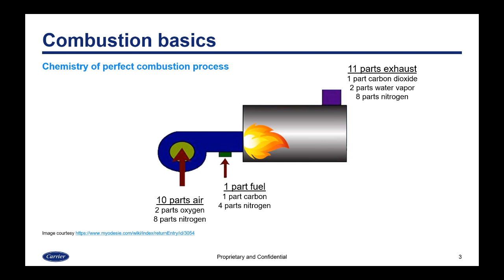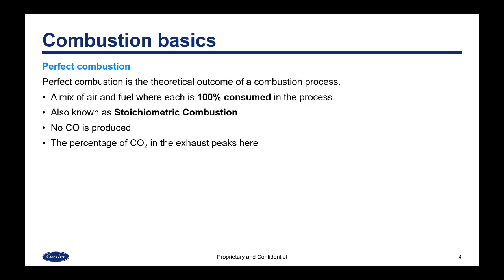This diagram shows how a perfect combustion process would work. You're going to have a component of air as well as a component of fuel, and together those are going to make up exhaust. Each air and fuel component is going to be made up of different chemical elements, as well as the exhaust. With perfect combustion — the theoretical outcome — all of the air and fuel would be consumed. This is also known as stoichiometric combustion, and with perfect combustion no CO is produced. The percentage of CO2 in the exhaust is at its highest with perfect combustion.